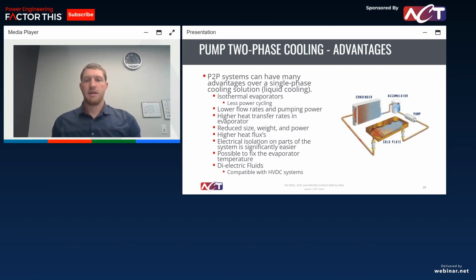So some of the advantages, one of the big ones that we see a lot of times is isothermal evaporators. Some of these IGBT, thyristor, or some of these really high flux components are very finicky on how you need to keep those cool and at what temperature they need to be held at. So one advantage that pump two-phase has is since you're operating at saturation, your evaporator is very isothermal across it, a matter of sometimes a degree or two across an entire cold plate. So all your components are going to be kept at the same temperature.